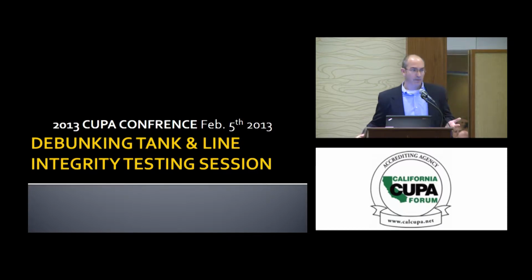I'm going to give a brief overview of the types of tests that were attempted on tanks. This is going back before my experience, before I was born, in fact. I heard stories about testing in the 60s using an air compressor, just hooking a hose up and putting pressure on that thing, see if it'll hold. These are stories that some contractors told me in the late 80s when I was working with them. They said, well, that's the way we used to do it. So every now and then you'd pop an end out of a tank, but that tank wasn't good anyway, or something like that.